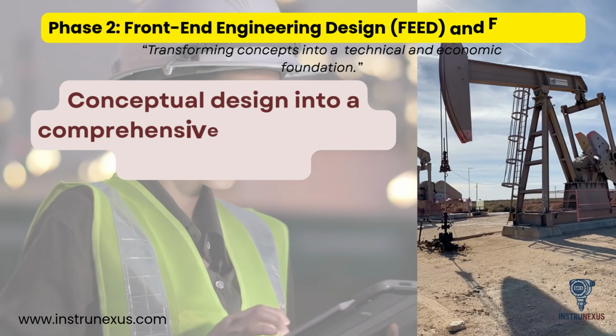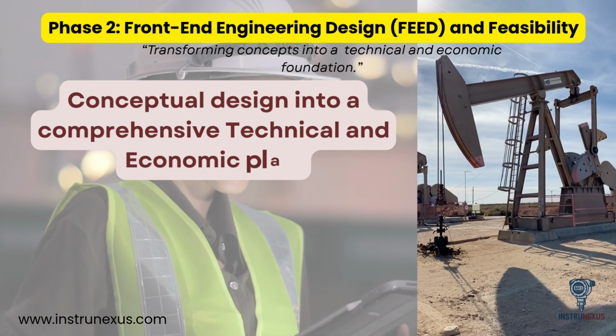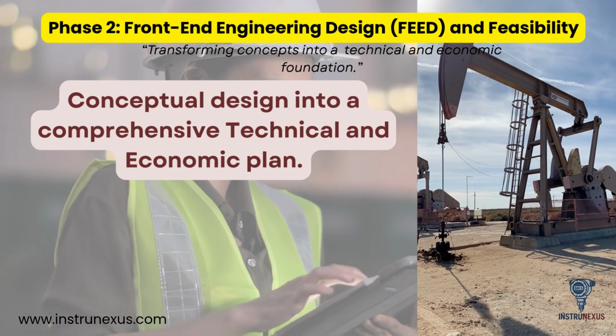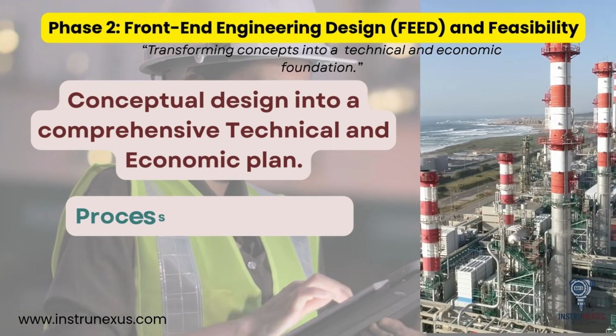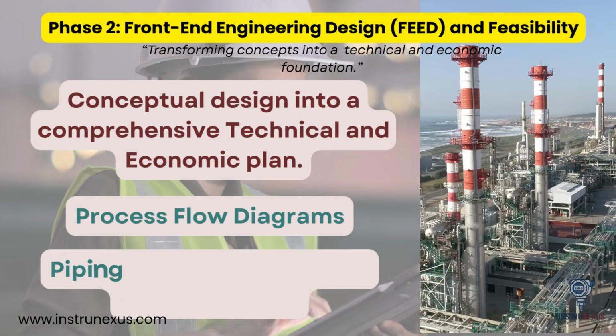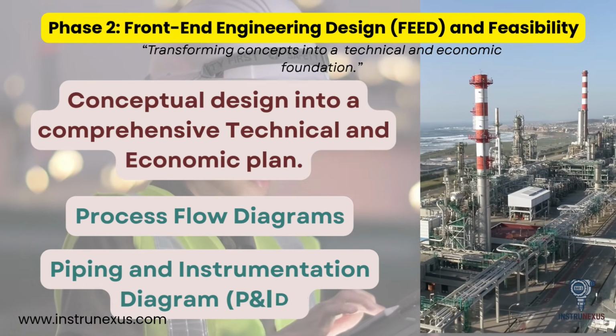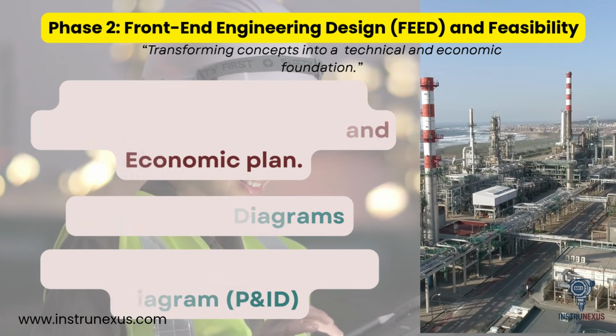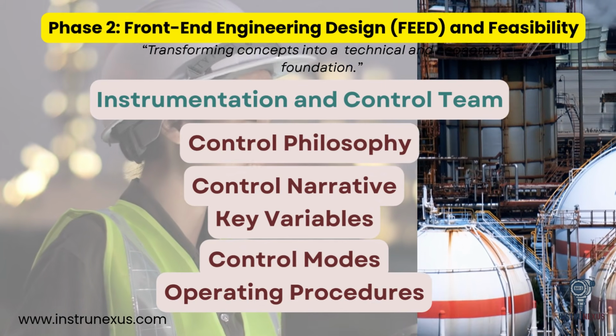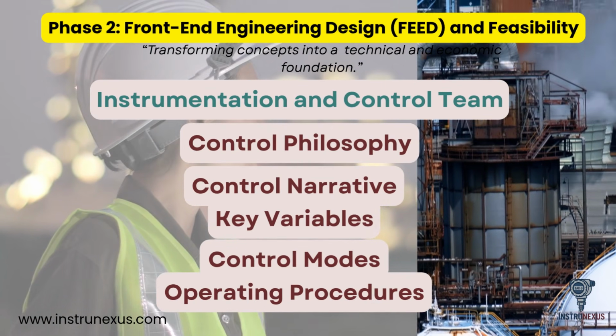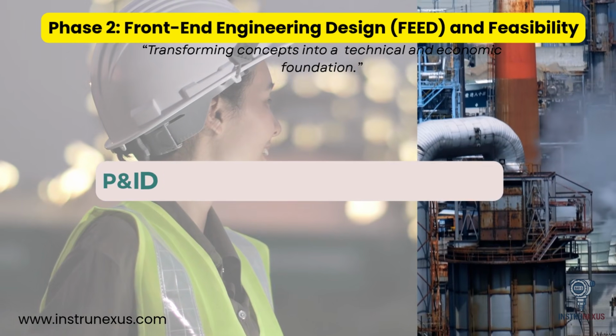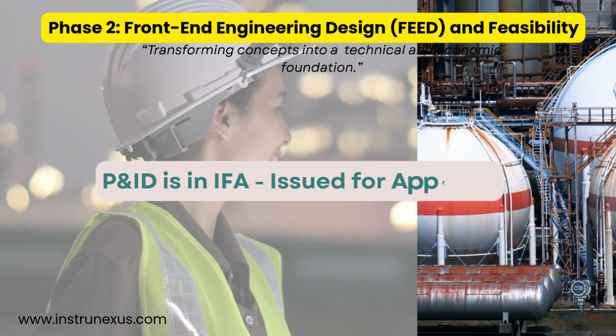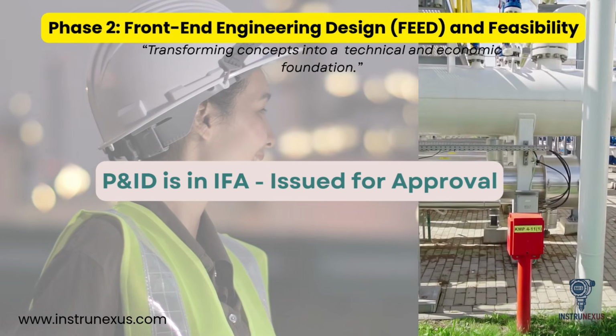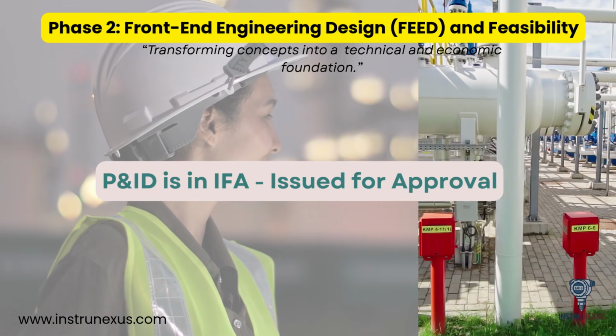The front-end engineering design, or FEED, refines the conceptual design into a comprehensive technical and economic plan. During this phase, engineers develop process flow diagrams and preliminary piping and instrumentation diagrams based on the heat and material balance from process engineering. The C&I team formulates the control philosophy and drafts the initial control narrative, defining how the plant will operate, the key variables, control modes, and operating procedures. At this point, the P&IDs typically progress to issued for approval, or IFA status, confirming alignment across all disciplines.